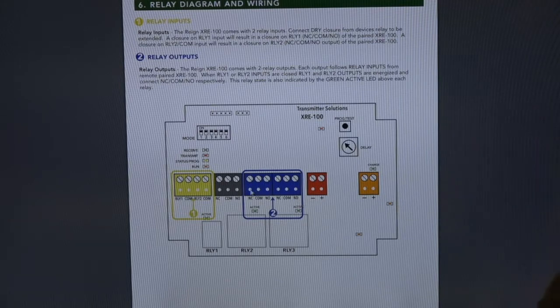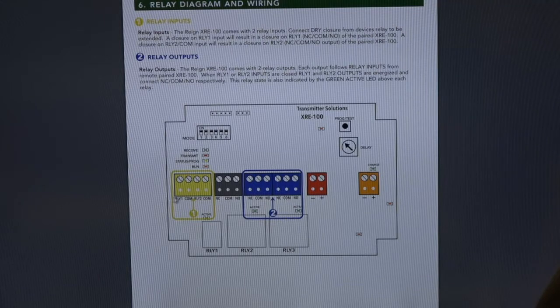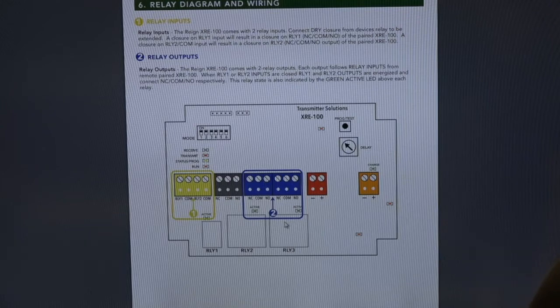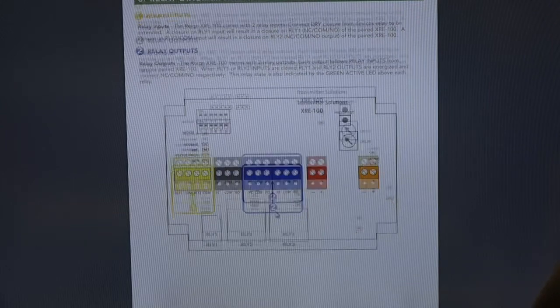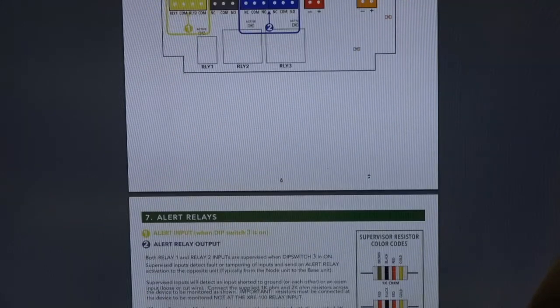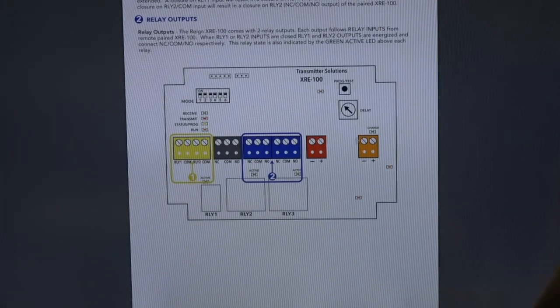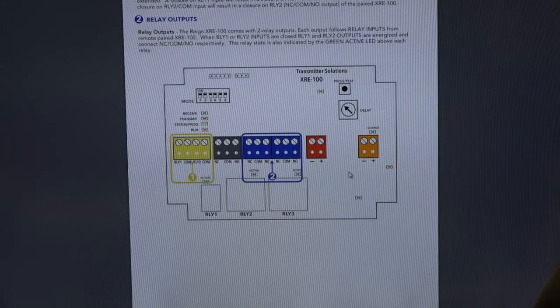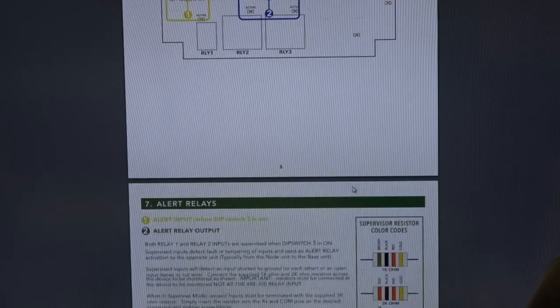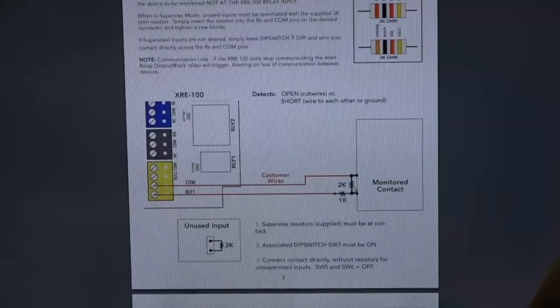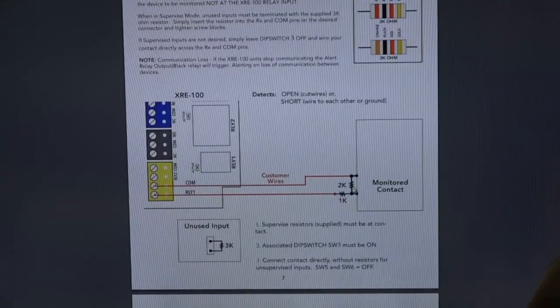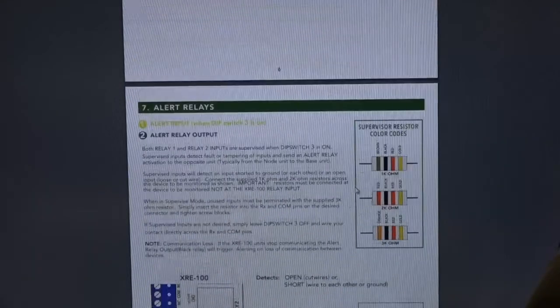Yellow is an input, blue is an output. So for every time you wire into a yellow, your corresponding output is a blue right here on that side. We have orange terminal is battery backup. Red terminal is your main power. And this will do 12 through 24 volt AC or DC, which makes it nice and easy to get power. And then we have gray.